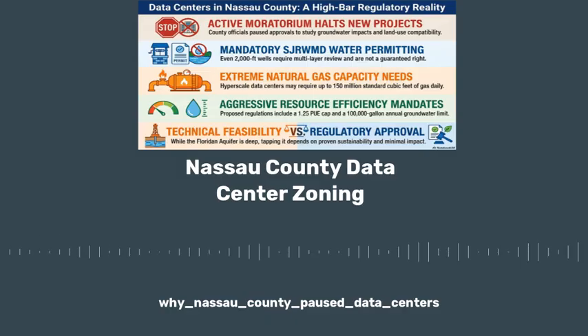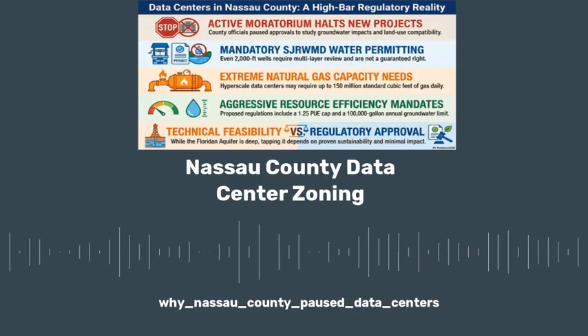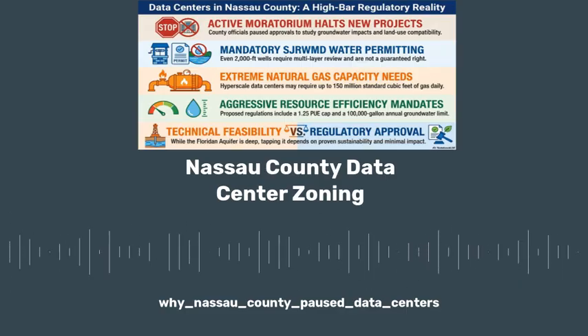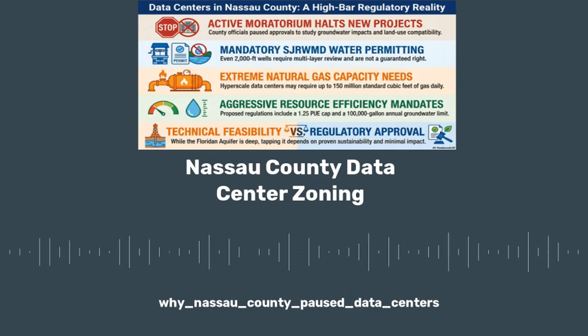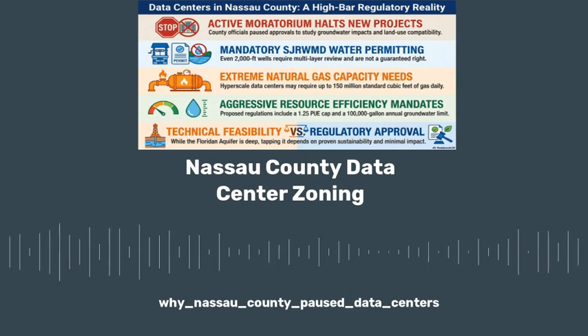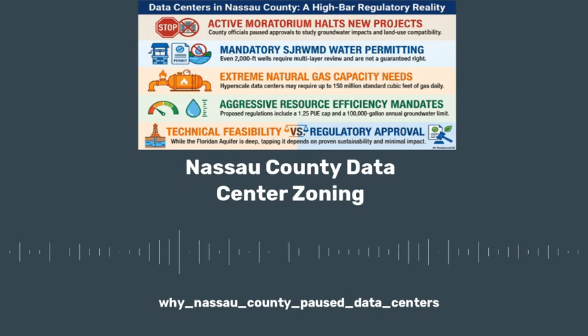But the new hyperscale facilities being designed for artificial intelligence training and massive cloud storage aren't 100 megawatts anymore. They're aiming for 1 gigawatt, which is 1,000 megawatts, meaning the natural gas requirement scales proportionally. A 1 gigawatt data center would demand between 100 to 150 million standard cubic feet of natural gas per day. That's 750 blimps of gas a day.